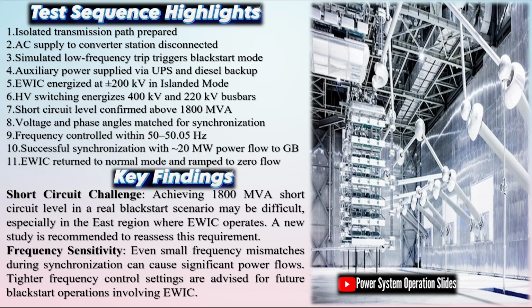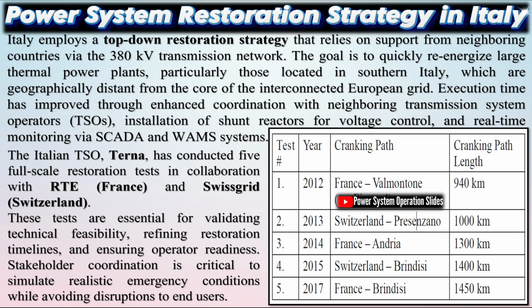Italy-Switzerland Power System Restoration Test. In 2013, Italy's transmission system operator Terna partnered with Swissgrid to conduct a top-down restoration test, building on earlier efforts with France. This test introduced 2 key advancements: use of shunt reactors only to energize a long-distance transmission path, and first successful synchronization of a power plant located 1,000 kilometers from the Swiss grid. The 1,000 kilometer transmission corridor ending at Presenzano station, south of Rome, was energized in just 13 minutes, followed by synchronization of the Presenzano unit 4 minutes later.